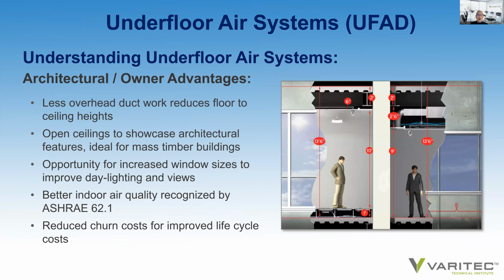our annualized hours. Owner advantages: less overhead ductwork, reduces floor-to-floor ceiling heights, open ceilings to showcase architectural features. These systems are ideal for a growing demand in our market for mass timber construction or mass timber buildings. There's an opportunity for increased window sizes to improve daylighting, better indoor air quality as recognized by ASHRAE 62.1, and we'll address that shortly, and reduce churn costs.